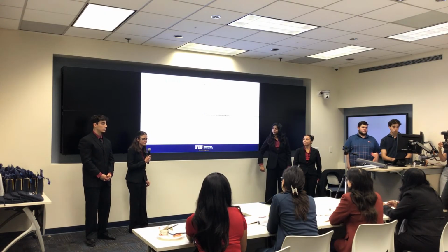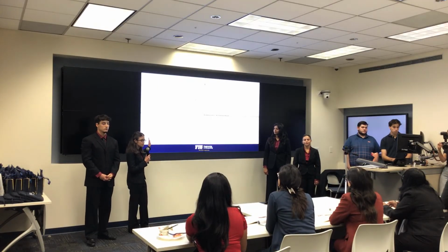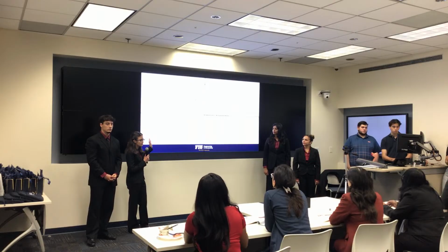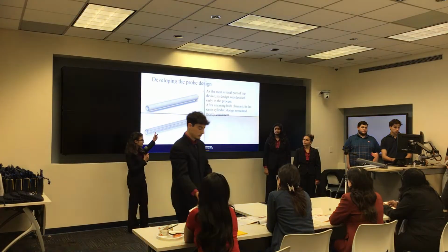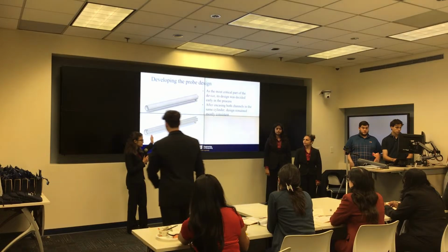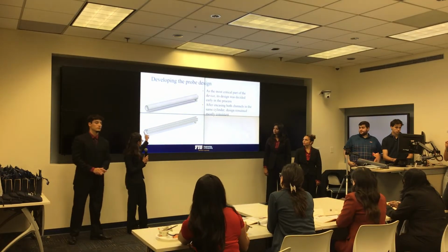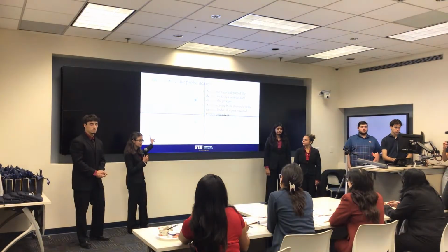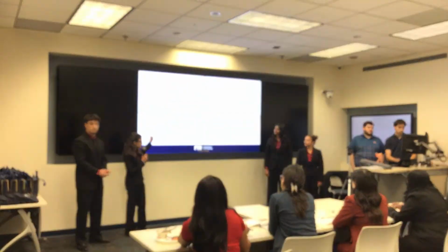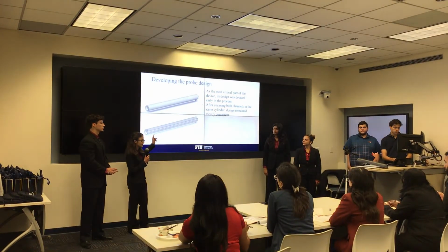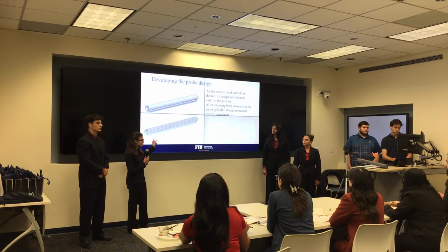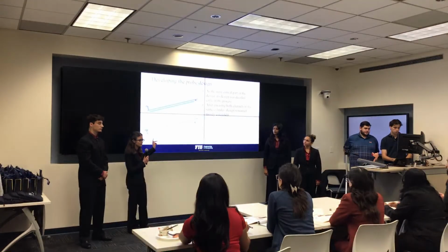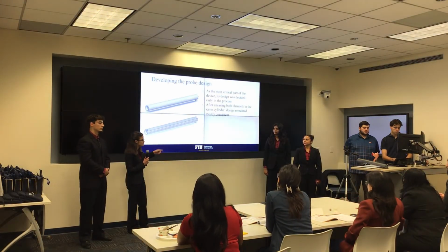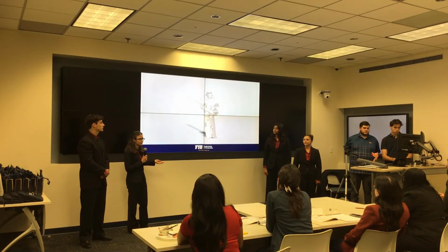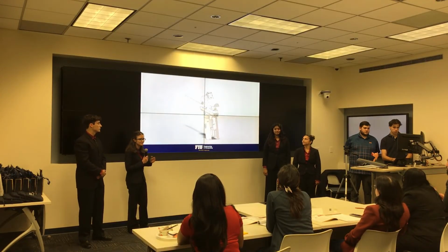The probe is the most critical part of the device, so I'll take a moment to explain how it works. The tissue would be here, and the probe is placed on the tissue. The pump generates suction through the suction channel you see here. As the pump generates suction, the tissue is displaced a 4 millimeter distance from the front of the probe chamber to the front of the suction channel lip. Meanwhile, the pressure sensor is sensing the changing pressure in the chamber through the bottom channel. Once the tissue is displaced the 4 millimeter distance, the pressure will stabilize, allowing you to take the reading. The pressure needed to reach a stable pressure reading depends on the stiffness of the tissue. And here, you can see an exploded view showing all of the internal components of our device.